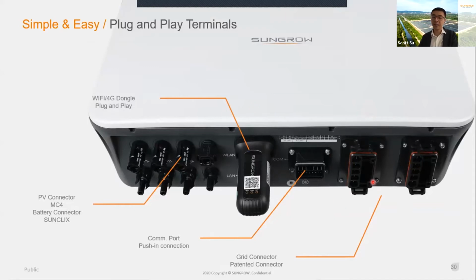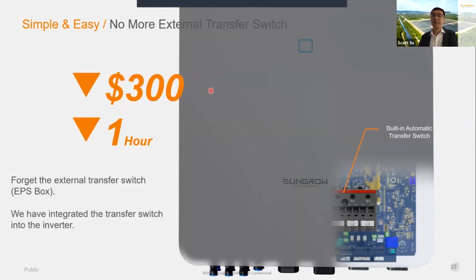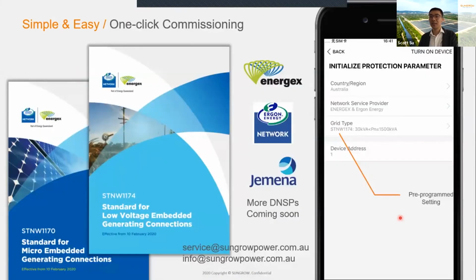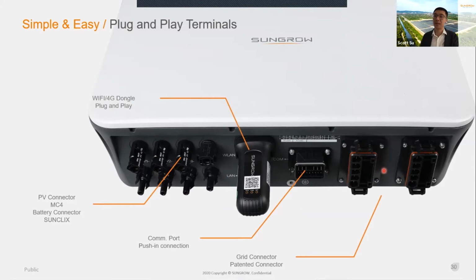The next one is we have plug and play terminals. This picture is very clear. We have an inbuilt EPS box with 2 AC terminals. This one is the backup circuit terminal, which will connect to the emergency circuits, I mean the sub switchboards and the emergency loads, and a third-party solar inverter can be installed on this circuit. The second one is the main AC circuit, which will connect to the grid. Here is the MC4 PV connector, and here is the battery connector.